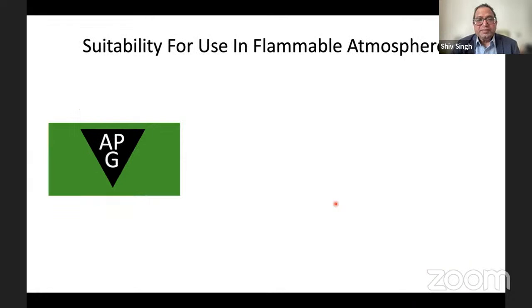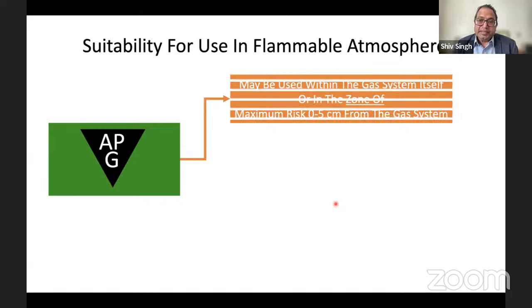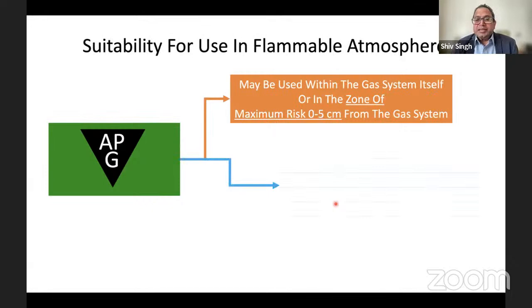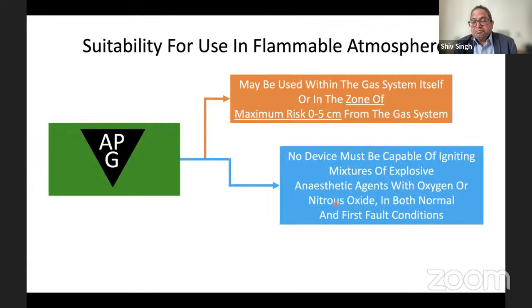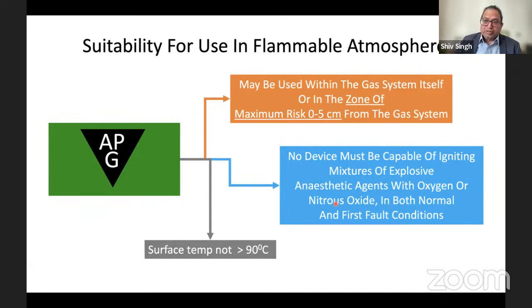APG is a lot more stringent. This equipment can be used in a zone of maximum 0 to 5 centimeters, where there is an oxygen-enriched environment, so there is a much higher risk of fire. These devices should not be capable of igniting a mixture of explosive anesthetic agents with oxygen or nitrous oxide. This should not happen even in normal conditions, or even if there is a fault, a leakage or a spark. And the allowable temperature of the body of the equipment is no more than 90 degrees. So that's how APG is defined.